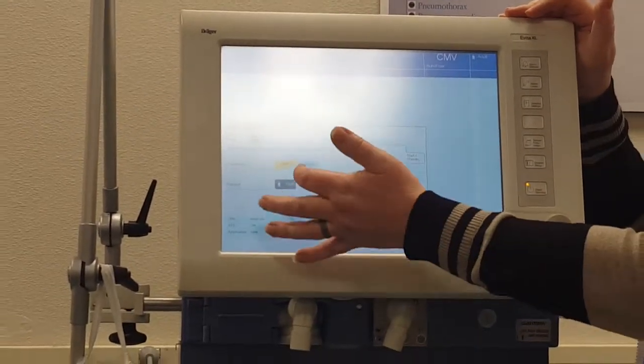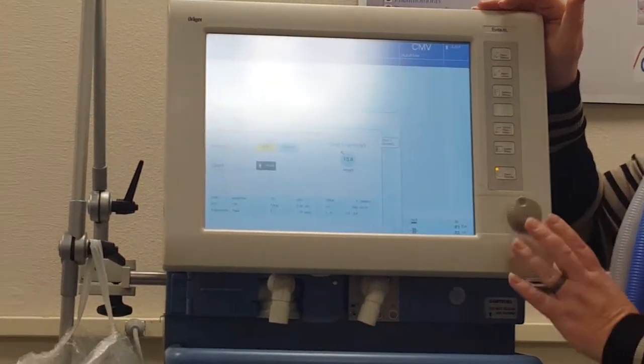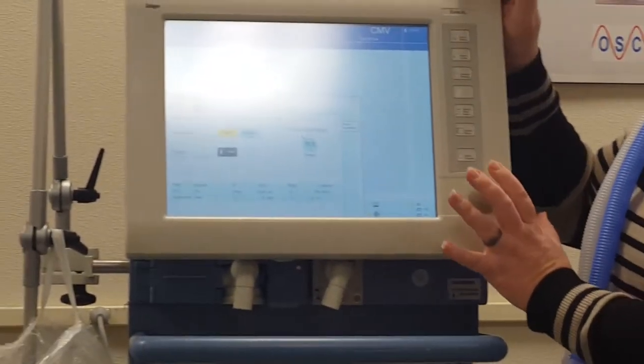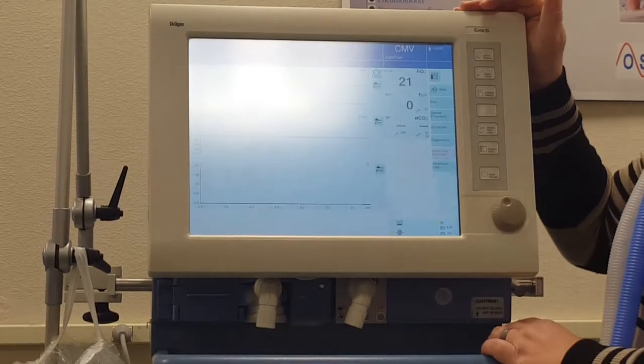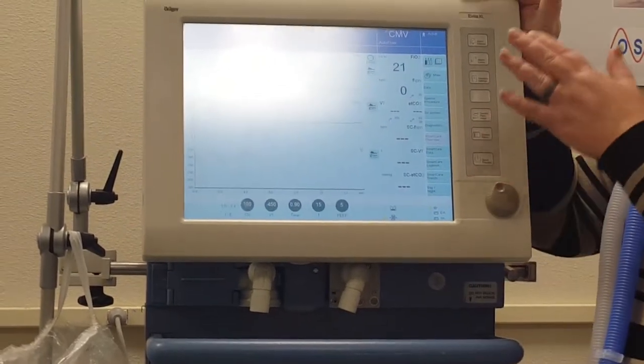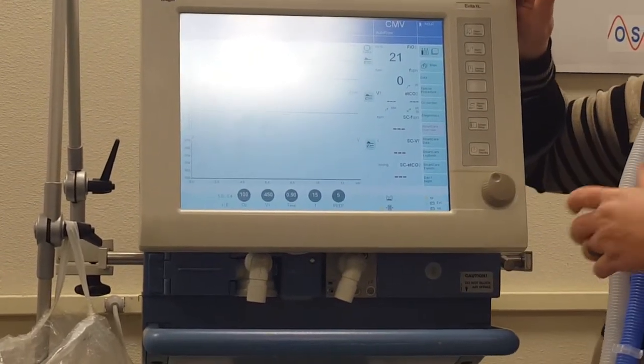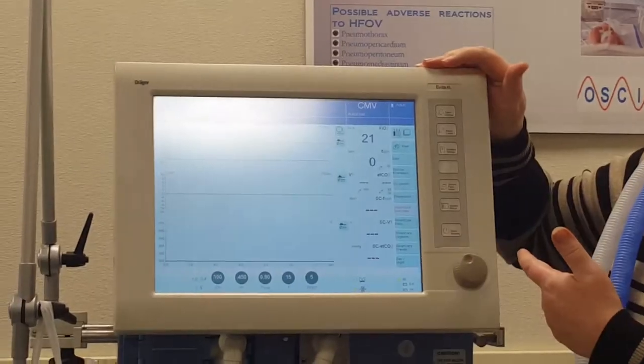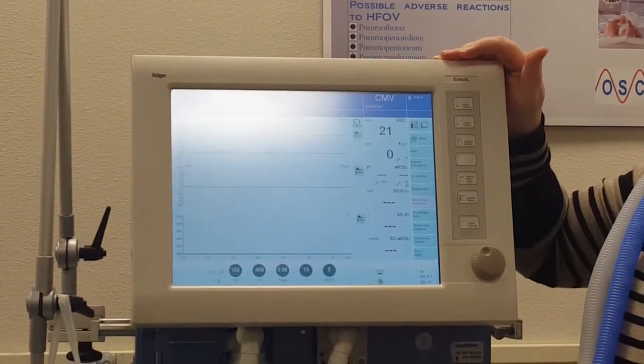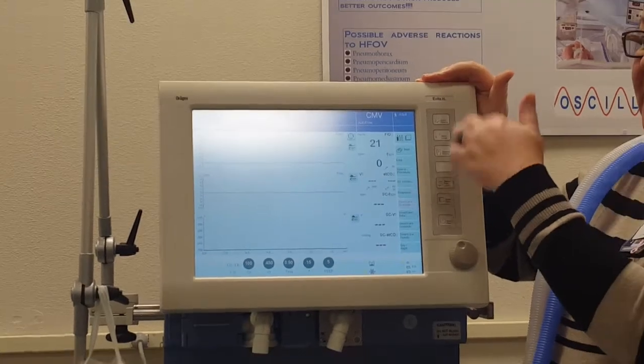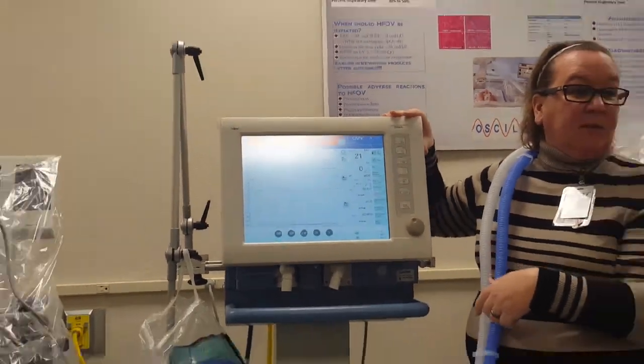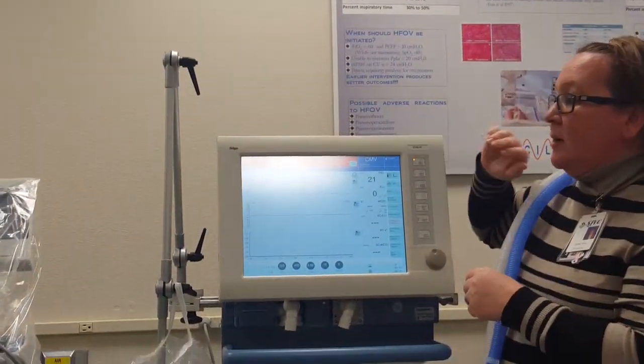With the DRAGER, it's touch screen. When you touch it, it turns yellow, and then the button over here confirms it and does what you want it to do. And then it would start ventilating. We have to calibrate this one. To calibrate it, you actually have to put it on standby, and it doesn't usually start in the right screen. So you want to turn it on, and now we're going to put it into standby so we can do the calibration. The standby on the DRAGER is a two-part.